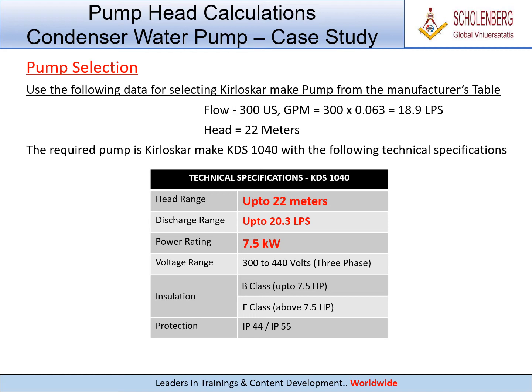Pump selection: Use the following data to select a Kirloskar make pump from the manufacturer's table. Flow: 300 USGPM equals 300 multiplied by 0.063 equals 18.9 LPS. Head: 22 meters. The required pump is Kirloskar make KDS 1040 with the following technical specifications.